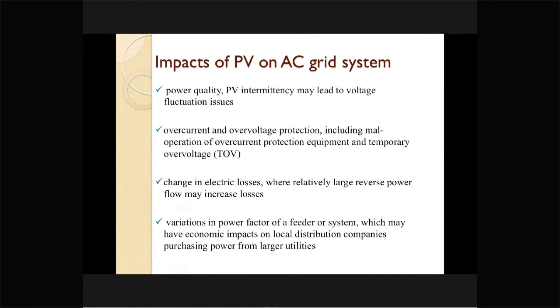Besides that, some more challenges could be power quality. PV intermittency leads to voltage fluctuation, and if the inverter is not proper, then it can cause harmonic injection into the system. Similarly, the overcurrent and overvoltage protection can also maloperate, and the overcurrent protection equipment needs to be properly designed, and the setting point has to be properly made, so that the integration of photovoltaic will be sustainable in nature. There may be some changes in the electric losses, that is power losses, and reverse power flow may also increase the loss.